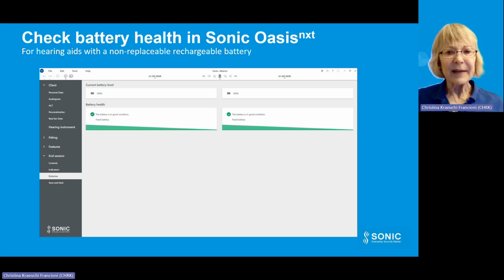I already mentioned previously that it is possible to check the battery health in the fitting software. You find the menu under End Session and Batteries. Express Fit Pro or Sonic Oasis Next will let you know if the battery is in good condition or if it needs to be replaced. For styles where the battery is not replaceable in the clinic, like we see in this picture, the hearing aid will need to be sent in for repair or service.